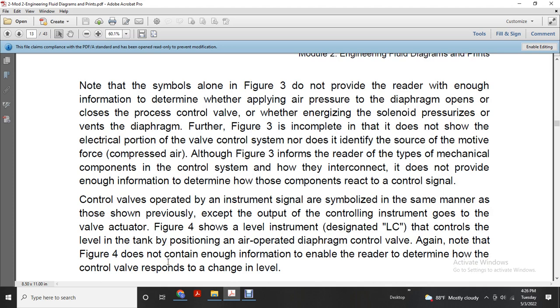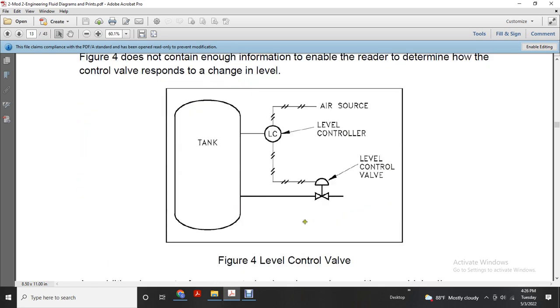The control valve is operated with an instrument signal, with the symbols shown previously, except that the output of the controlling instrument goes to the valve actuator. Figure 4 shows a level instrument designated LC, controlling the level in a tank by positioning an air-operated diaphragm control valve. Again, note that figure 4 does not contain enough information to enable the reader to determine how the control valve responds to a change in level. It shows the tank and the level controller, with the air source and level controller valve with the diaphragm solenoid.